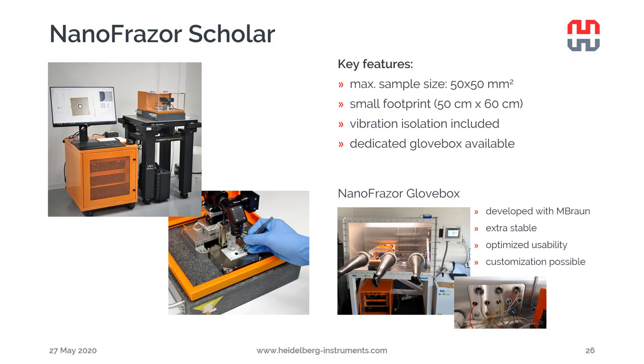The NanoFrazor Scholar has a separate housing for the writing head and the electronics. It can pattern samples as large as 50 mm by 50 mm in size. Before, our customers had to prepare their own vibration isolation, but now we always include an active vibration isolation in the system. The Scholar is less robust against acoustic noise compared to Explore, so to work properly and achieve all the specifications, the noise level in the lab should be less than 40 dB.